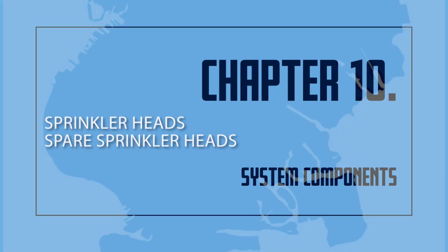After activation by fire, sprinklers in close proximity to the affected heads are recommended to be replaced. A stock of spare sprinklers, not less than 6, shall be kept on the premises where the temperature does not exceed 100 degrees Fahrenheit, and shall include all types and ratings installed in the protected facility and provided as follows.